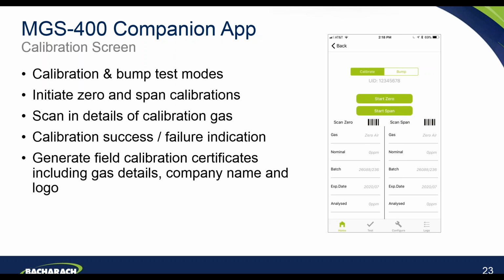This is a great feature, particularly for those within our channels and our customers who have service as part of their business model. It automatically generates a field calibration certificate for that detector. It will use all the information of the gas and the calibration and the unit itself to populate a calibration certificate for the instrument, including gas details. A unique feature here is that you can incorporate your own company name and logo within that calibration certificate, so that when you send that across to your customer, rather than it being a Bacharach branded document, it's fully branded with your company logo and your company details.